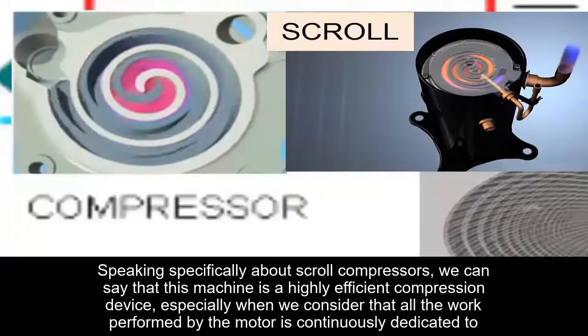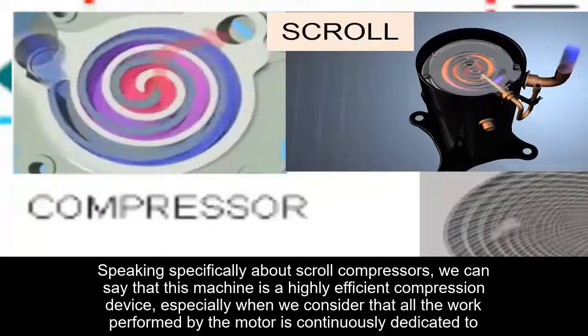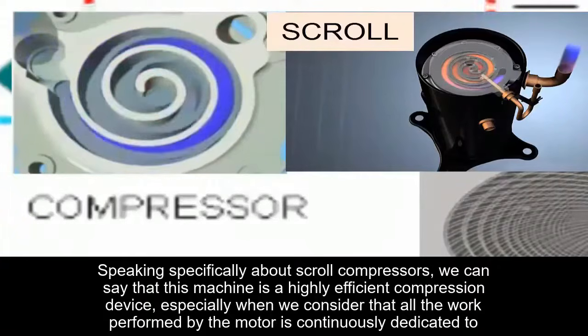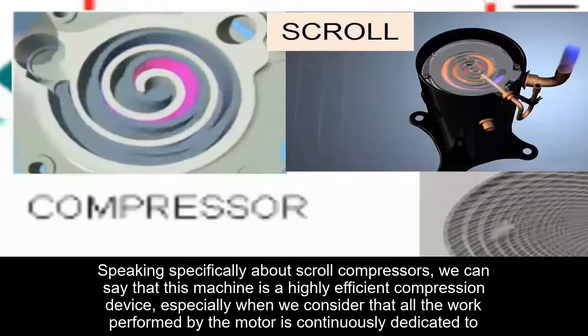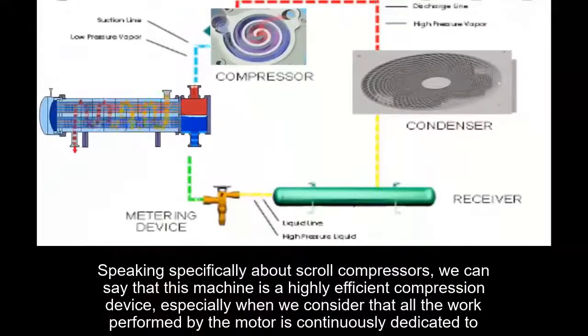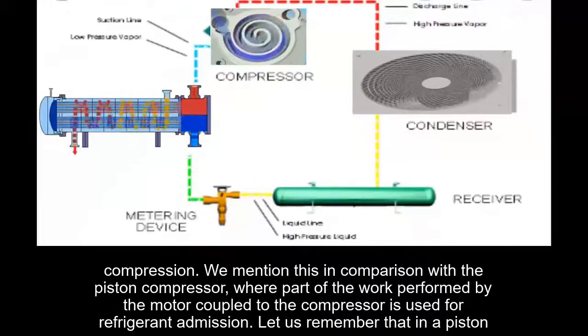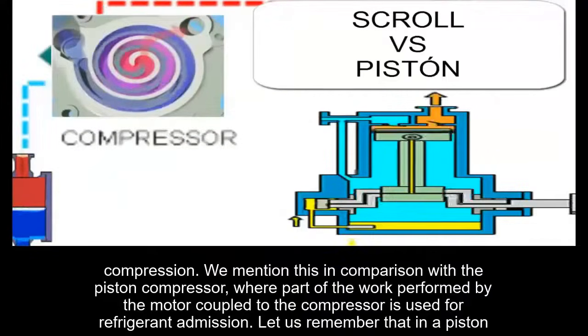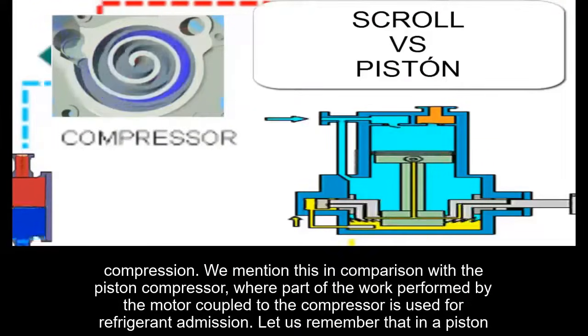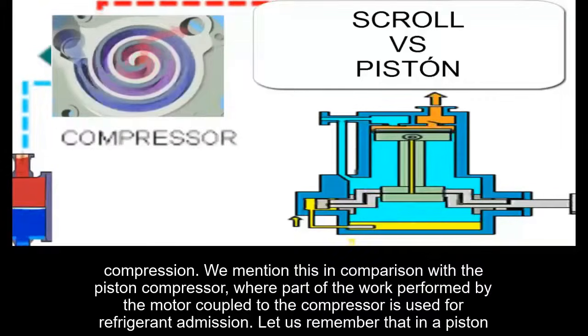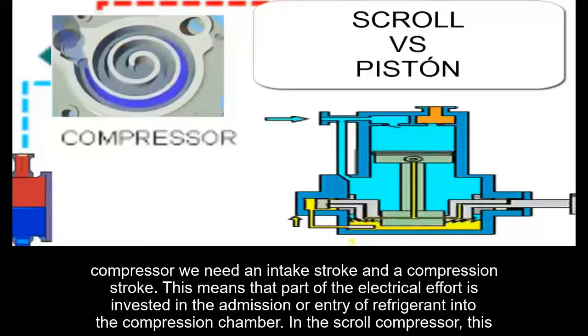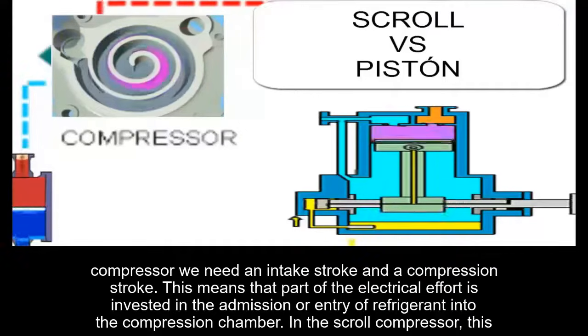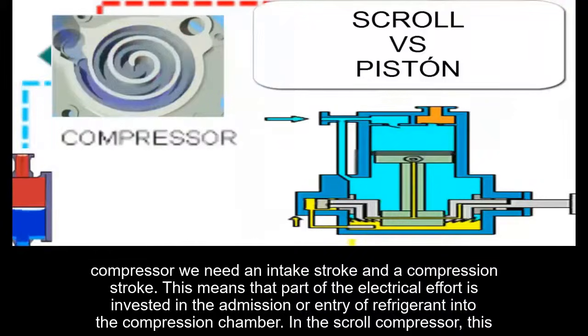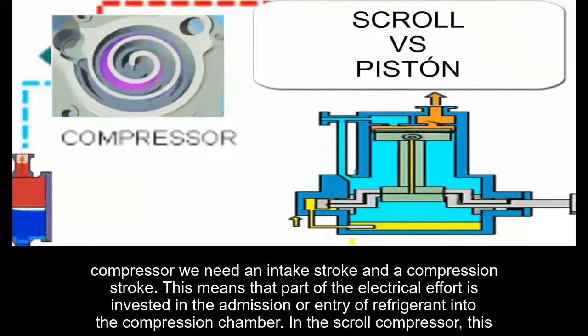than 4 scroll-type compressors. Speaking specifically about scroll compressors, we can say that this machine is a highly efficient compression device, especially when we consider that all the work performed by the motor is continuously dedicated to compression. We mention this in comparison with the piston compressor, where part of the work performed by the motor, coupled to the compressor, is used for refrigerant admission. Let us remember that in a piston compressor, we need an intake stroke and a compression stroke. This means that part of the electrical effort is invested in the admission or entry of refrigerant into the compression chamber. In the scroll compressor, this does not occur in the same way.